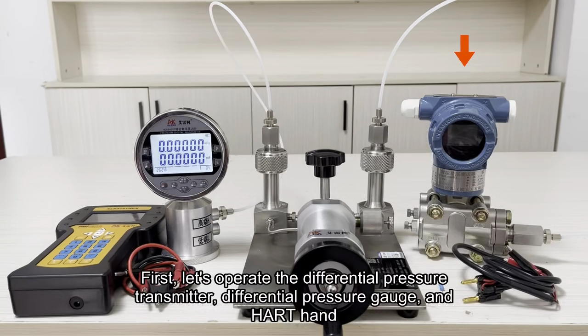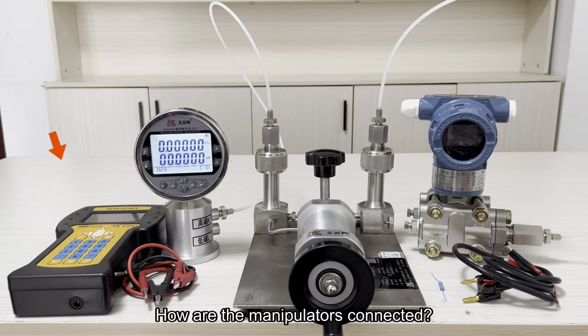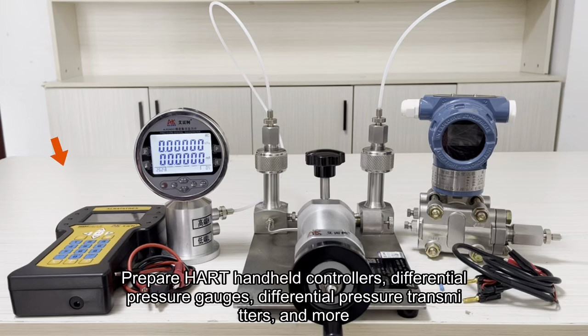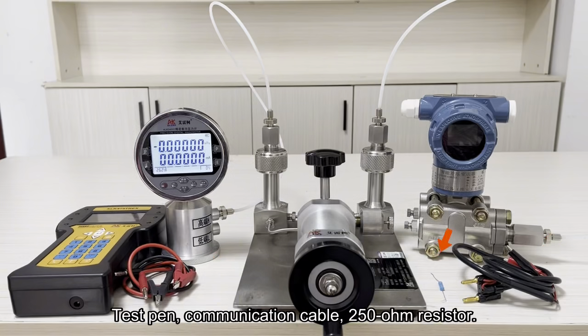First, let's operate the differential pressure transmitter, differential pressure gauge, and HART handheld controller. How are they connected? Prepare the HART handheld controller, differential pressure gauge, differential pressure transmitter, test pins, communication cable, and a 250 ohm resistor.